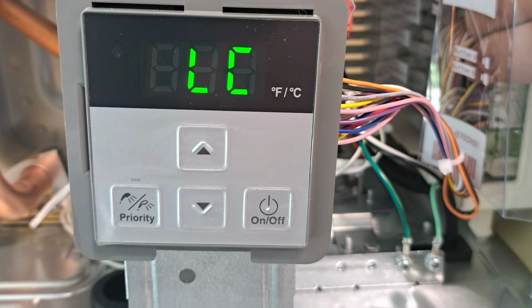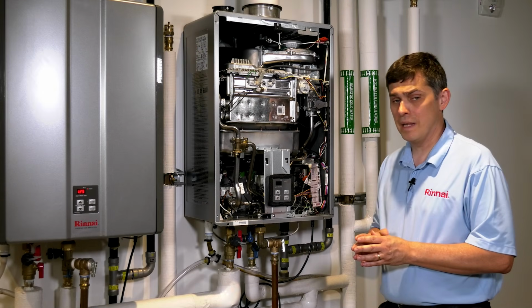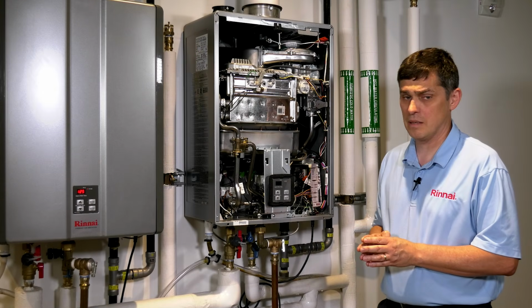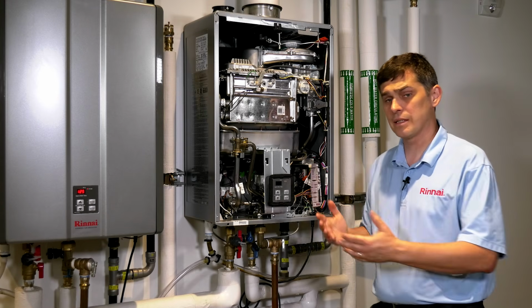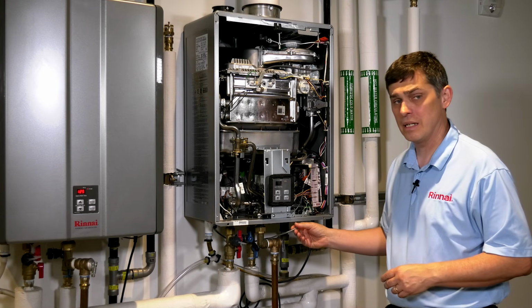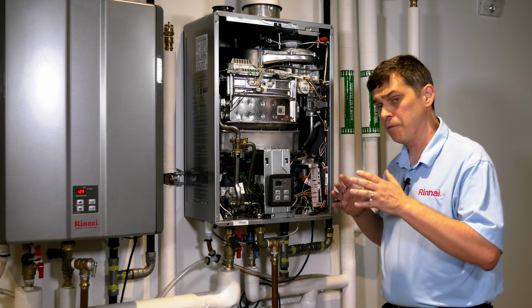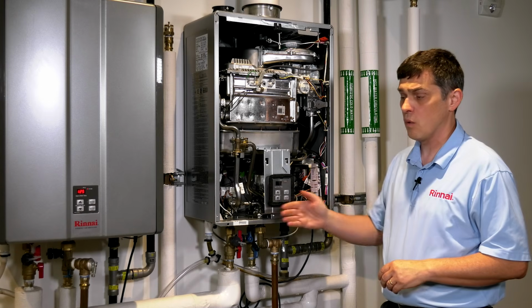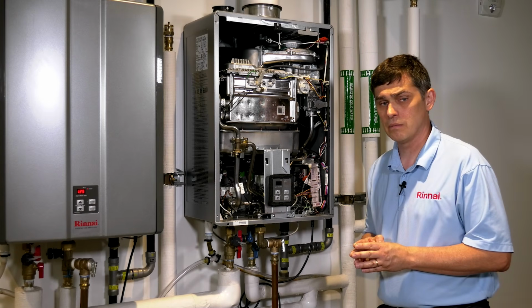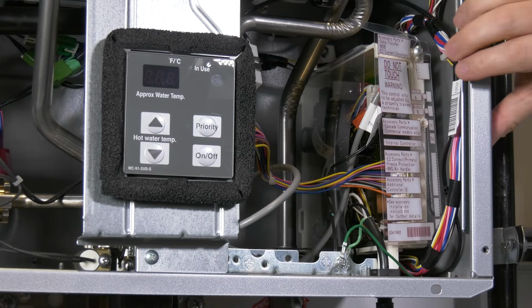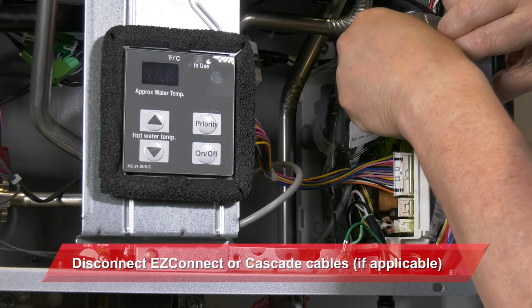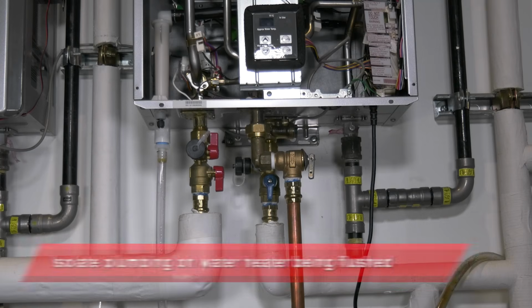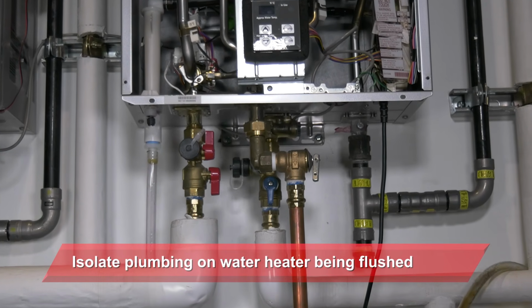So we're in front of two Rinnai Sensei tankless condensing models, and they work together as a single system using what's called an Easy Connect cable. Now we can actually flush one of these units while the other one remains in operation. With power removed, we'll disconnect the Easy Connect cable. We're also going to isolate the water heater we're flushing from the plumbing system.